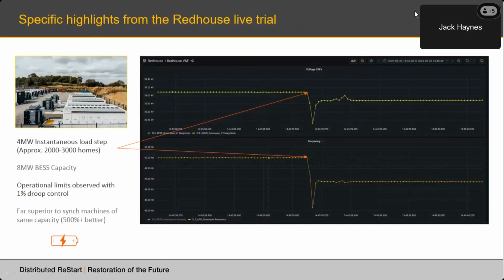So the first one was that key figure I talked about, the block load pickup capability. What's the maximum load we can switch on in one step whilst the island maintains stability? Generally the understanding of the threshold was that the frequency deviation didn't drop below 47.5 hertz. Now we had a 4 megawatt load bank at our disposal, and we gradually stepped the load bank up in larger steps, and it was pretty immediately apparent that the BESS was able to cope with load steps of those sizes very well.